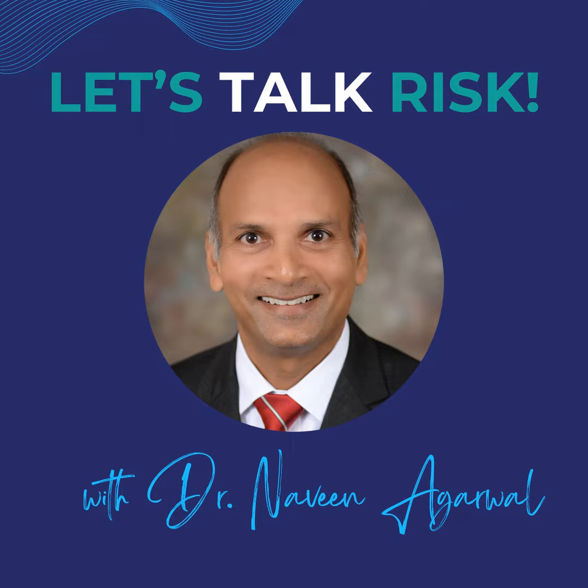I saw a good breakdown of transparency that talked through data transparency about what's going into it, algorithm transparency about just that mental model or logic, performance transparency about accuracy and limitations, and clinical transparency about making decisions based on that information. So I think just thinking through and making sure that those considerations are addressed in the risk file, are evaluated, and then appropriately mitigated and evaluated, whether it's through human factors testing or other NIST standards and other things that provide guidance.